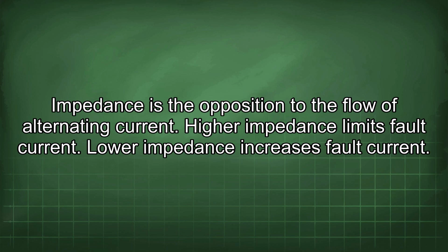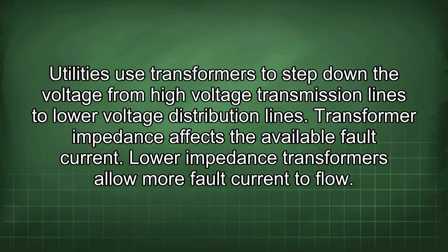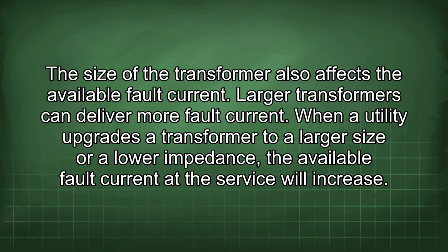Higher impedance limits fault current. Lower impedance increases fault current. Utilities use transformers to step down the voltage from high voltage transmission lines to low voltage distribution lines. Transformer impedance affects the available fault current. Lower impedance transformers allow more fault current to flow. The size of the transformer also affects the available fault current. Larger transformers can deliver more fault current.